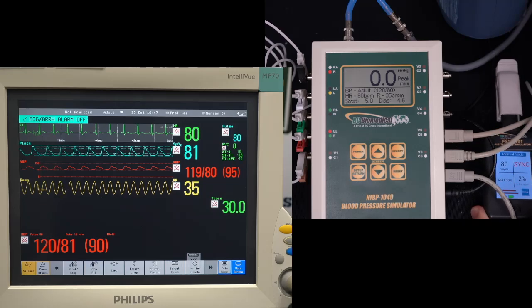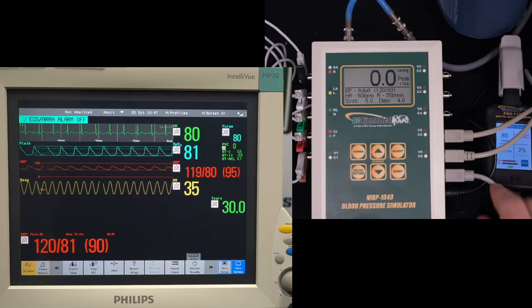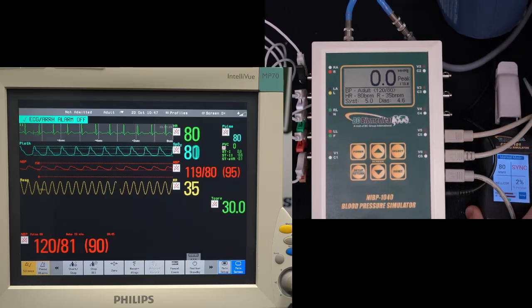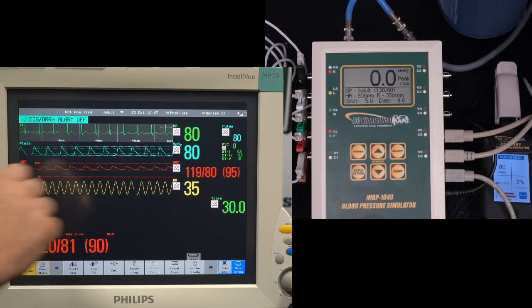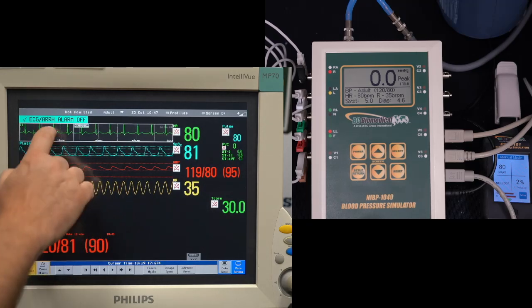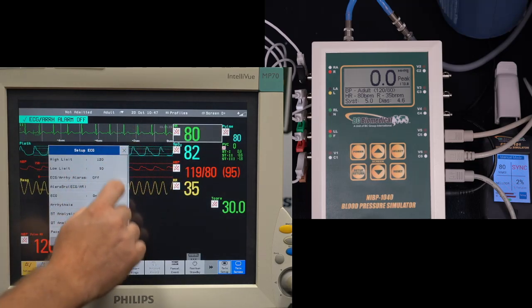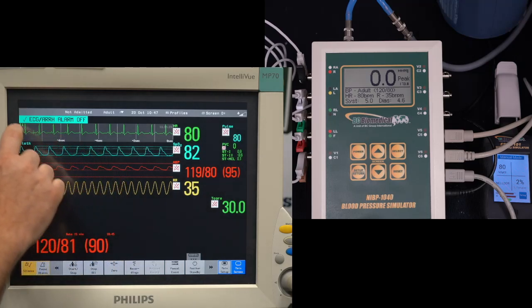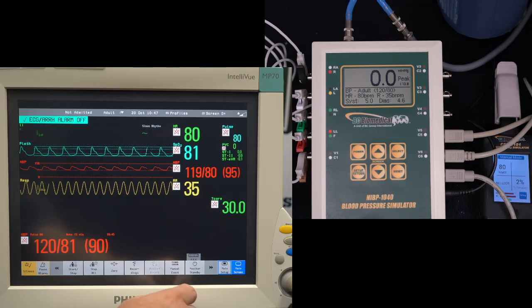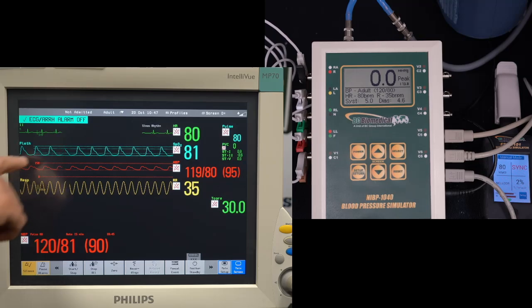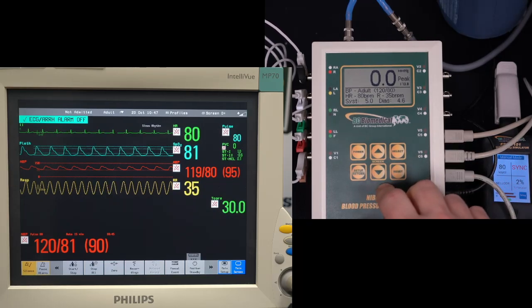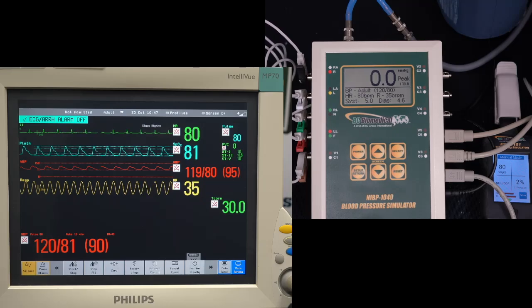I mentioned the FSX-1101, so that's connected here. Now I do have the sync cable plugged in, and this allows me to get synchronized SpO2 with my ECG. And it looks like, let me see if I can get my ECG to update here. I don't know why that's not behaving for me. Unfreeze. There we go. So now we've got our ECG waveform, and the SpO2 is synchronized with that. Now, if I were to disconnect that cable, I would still get an SpO2, but then the heart rate wouldn't be synchronized with the NIBP. So that's another simulation that we have there.